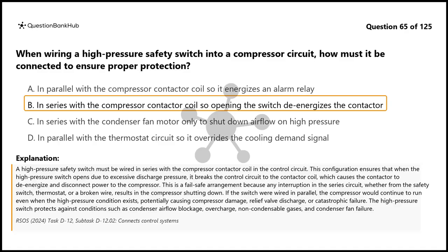This is a fail-safe arrangement because any interruption in the series circuit, whether from the safety switch, thermostat, or a broken wire, results in the compressor shutting down. If the switch were wired in parallel, the compressor would continue to run even when the high-pressure condition exists, potentially causing compressor damage, relief valve discharge, or catastrophic failure. The high-pressure switch protects against conditions such as condenser airflow blockage, overcharge, non-condensable gases, and condenser fan failure.